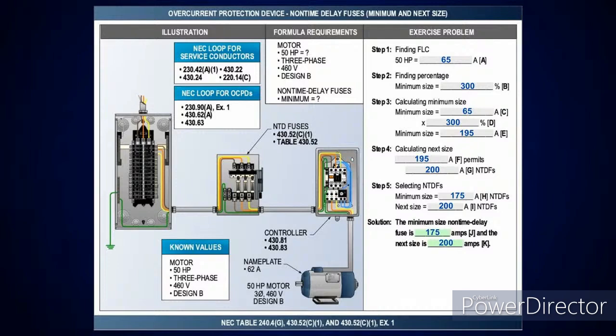I mean, even when NFPA published our books, the table still stated the same in 430.52, and it says maximum, but that's the maximum percentage for that table. And you got people like Jeremy and Ted and all of them, they come in, that ain't right, there's no maximum, there's no minimum. And I'm like, I don't know what y'all arguing about. You going to tell me that the staff at NFPA is all incorrect too? Because they added it. We had 3 editors at NFPA looking at the technical validity of what we published, and it's been in the books that way 30 years. I mean, now all of a sudden it's wrong because they say so. And when have you ever heard about having 2 maximums?